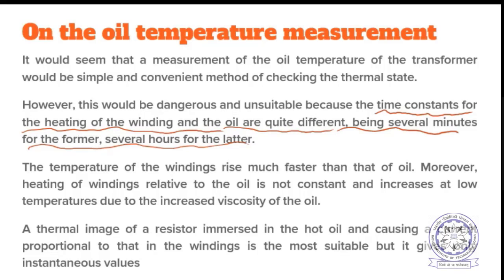The temperature of the windings rises much faster than that of the oil. Moreover, the heating of the windings relative to the oil is also not constant. For example, at low temperatures and high temperatures, the relative heating of the windings is different, actually due to the viscosity of oil, which is a temperature dependent property. So due to these problems, sensing oil temperature and telling about the condition of the transformer is not a good idea. But what is a good idea?